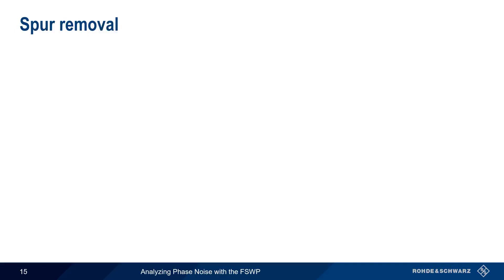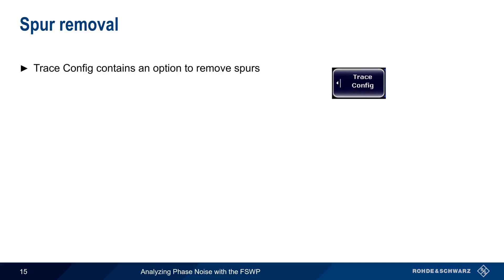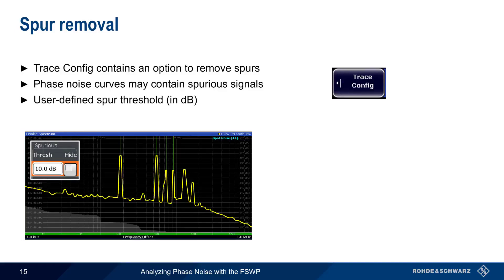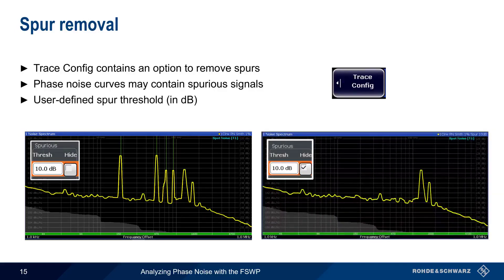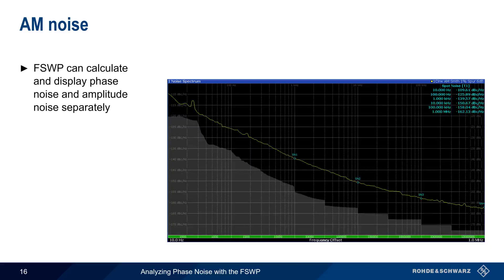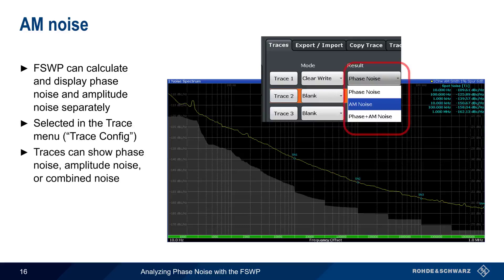Another display feature is spur removal, also enabled under Trace Config. Many phase noise curves contain spurious signals, which appear as peaks or spikes on the trace. Spurious signals are caused by interfering signals, not by phase noise, so we often want to remove them from our results. This is done by defining a threshold in dB — enabling spur removal hides spurs which lie more than this number of dB above the trace. Additionally, the FSWP can separate phase noise and amplitude noise and display either the combined result or plot them separately, selectable via the Trace Config menu.